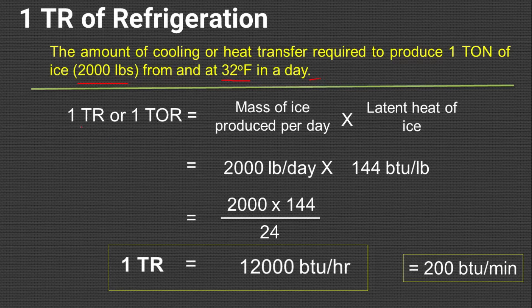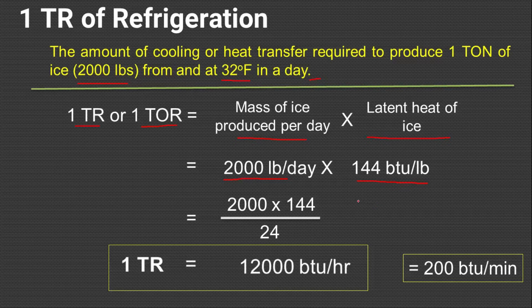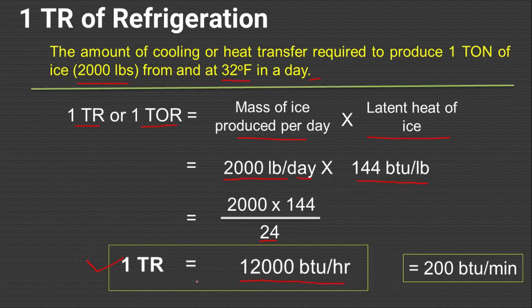1TR of refrigeration, which is also 1TOR, is equal to mass of ice produced per day multiplied by the latent heat of ice. The mass of ice produced is 2,000 pounds per day, multiplied by 144 BTU per pound, which is the latent heat of ice. So 2,000 pounds per day is converted to pounds per hour as 2,000 divided by 24, and it is multiplied by 144, which gives 12,000 BTU per hour — which is 1 ton of refrigeration.